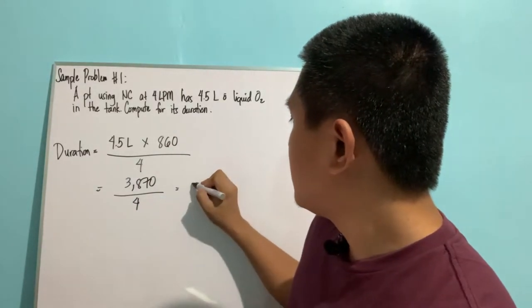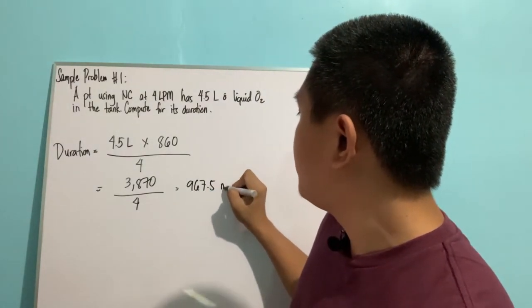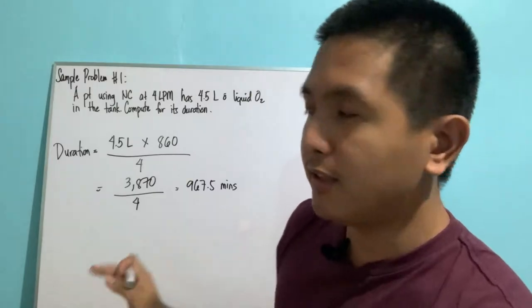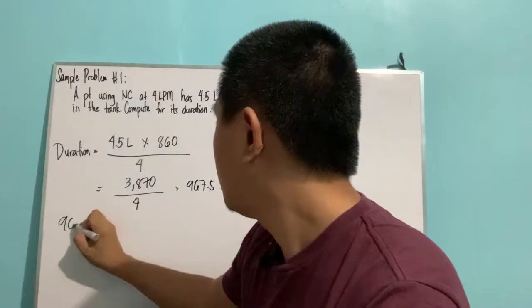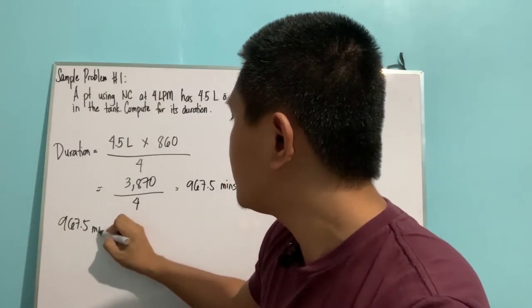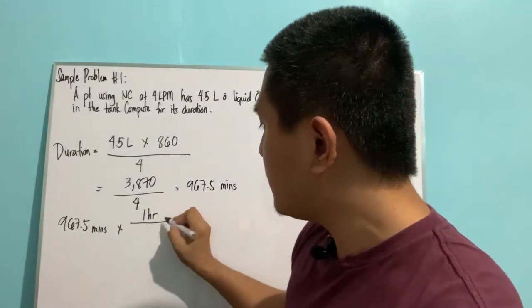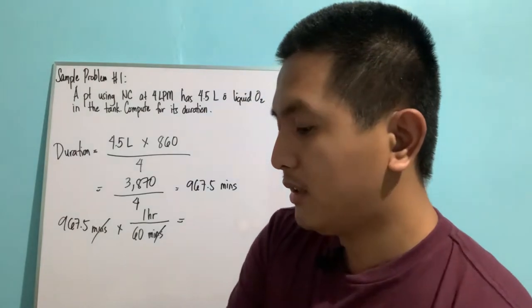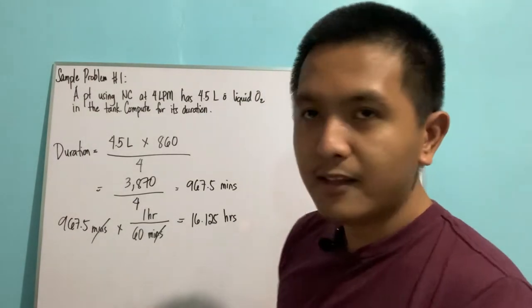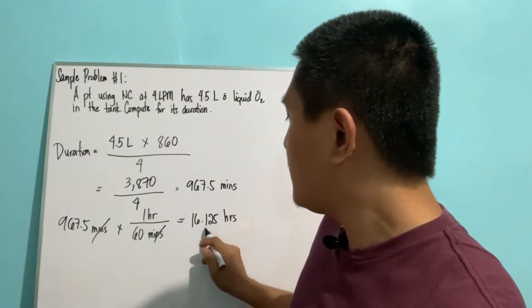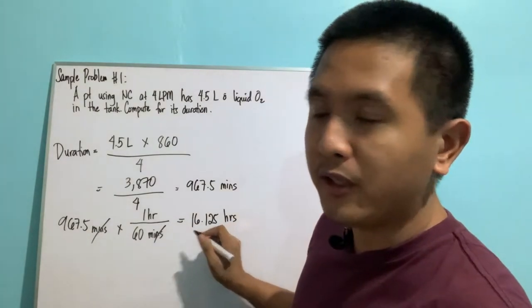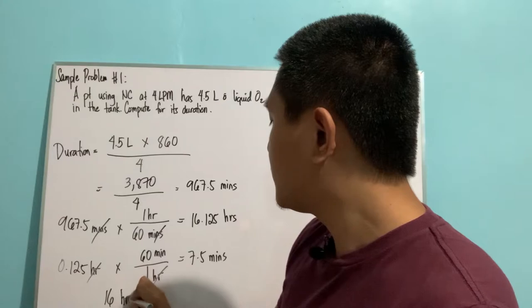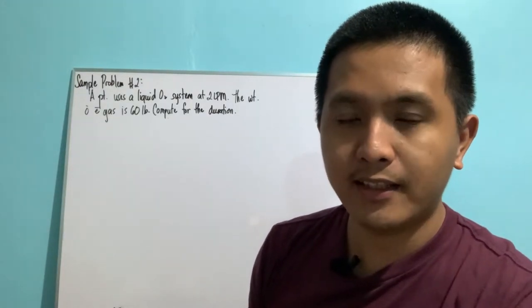Using a calculator: 4.5 multiplied by 860 gives us 3,870. Divide by 4 and we get 967.5 minutes. In your licensure exam you may be required to convert this into hours. 967.5 divided by 60 is 16.125 hours. Convert the decimal: the duration for 4.5 liters of liquid oxygen running at 4 liters per minute is 16 hours and 7 minutes.